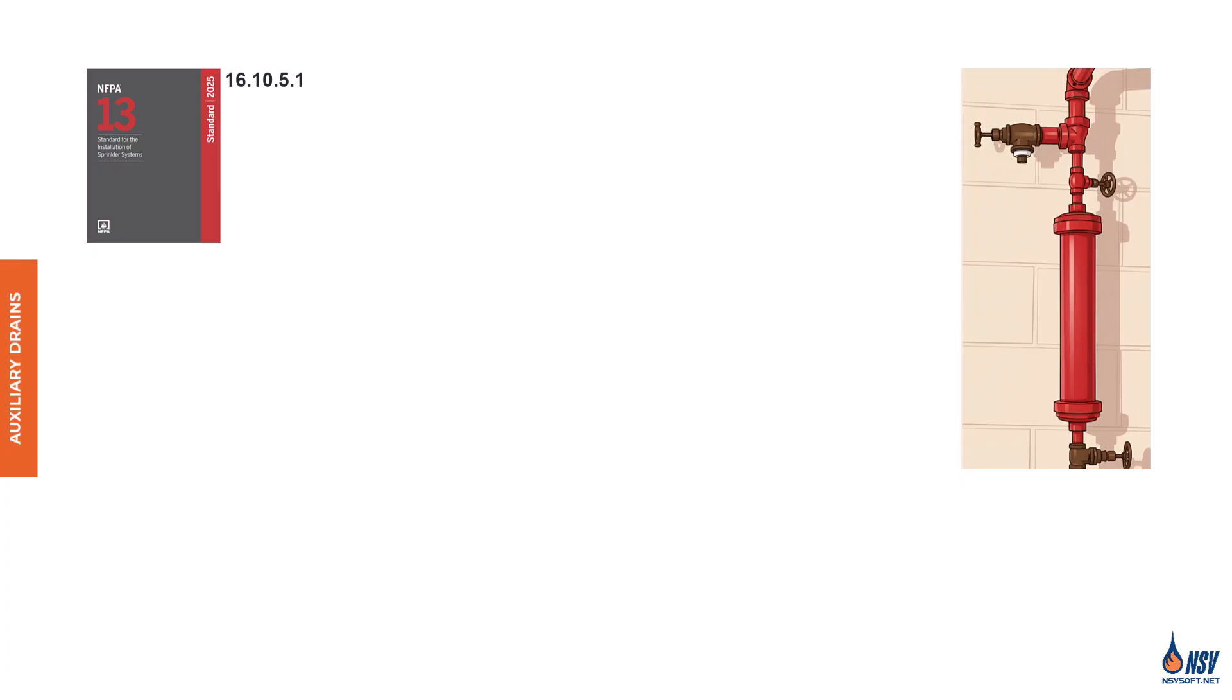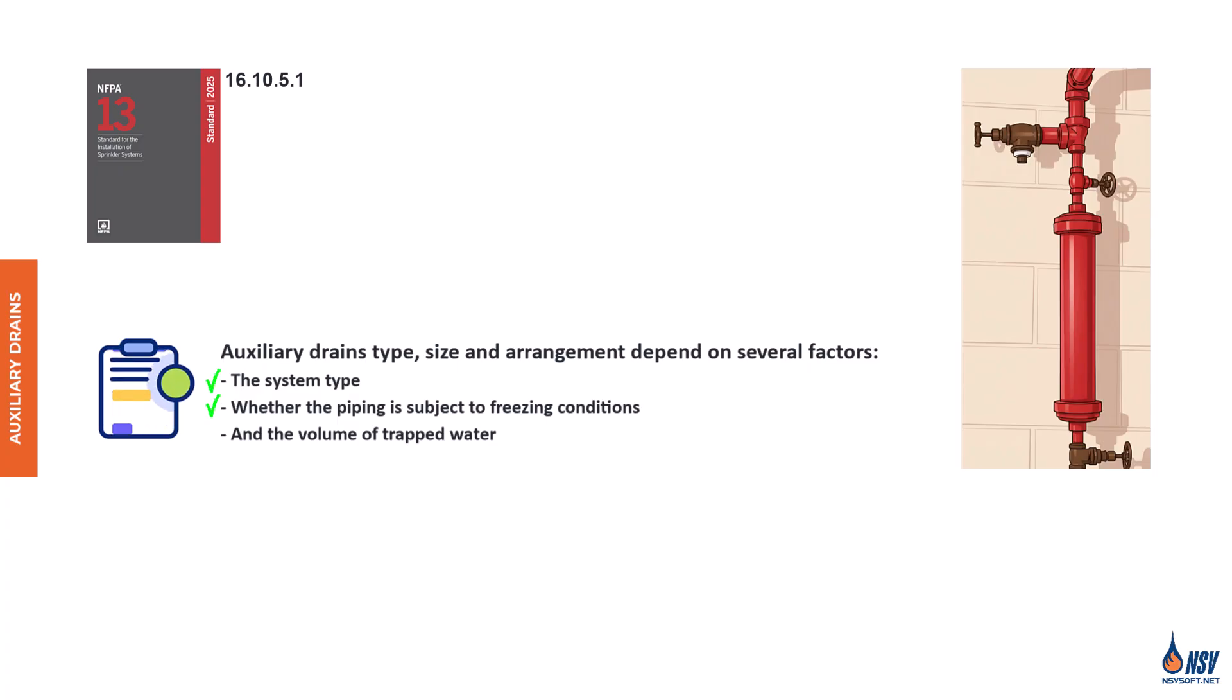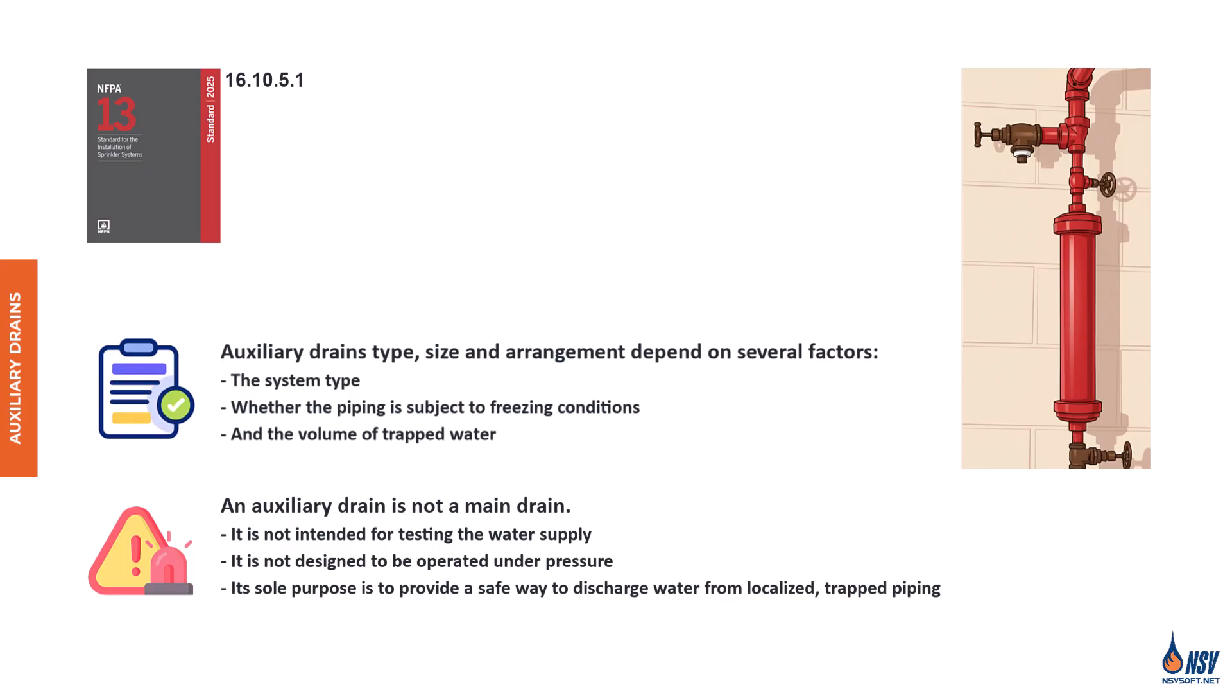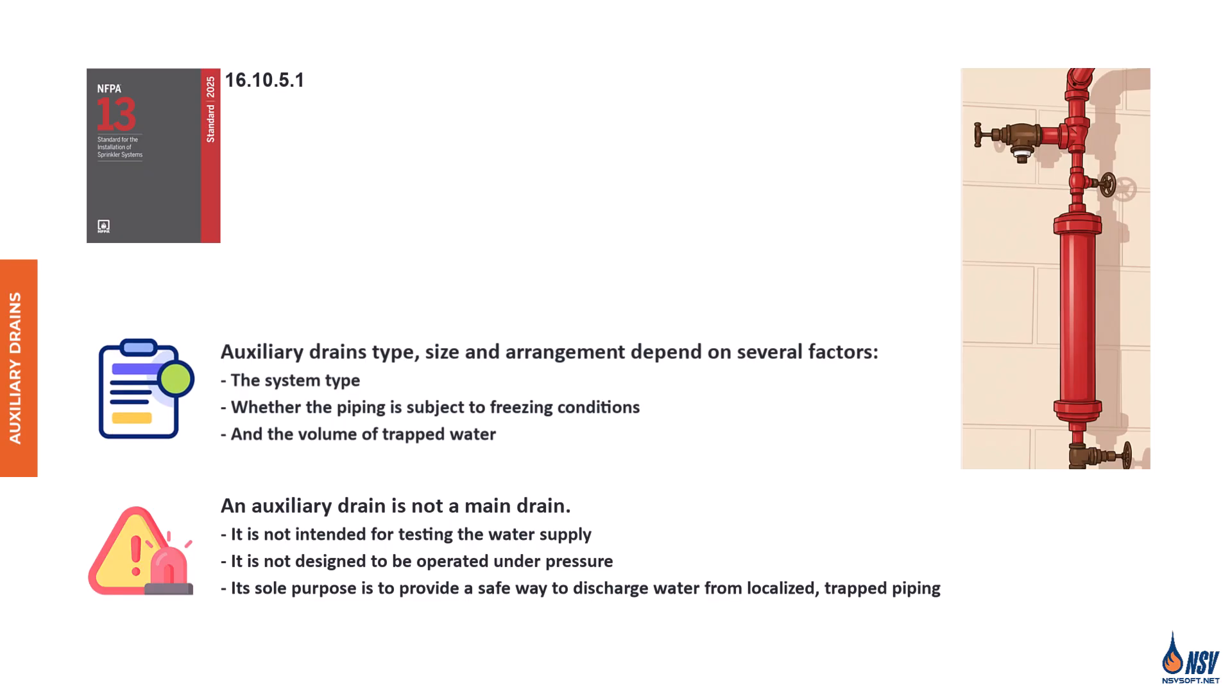According to Section 16.10.5.1 of NFPA 13, 2025 edition, auxiliary drains are defined as drain connections installed to remove water from a trapped section of pipe. They shall be provided wherever a change in piping direction prevents drainage of system piping through the main drain valve. Auxiliary drains are essential for trapped piping. Their type, size, and arrangement depend on several factors: the system type, whether the piping is subject to freezing conditions, and the volume of trapped water. An auxiliary drain is not a main drain. It is not intended for testing the water supply. It's not designed to be operated under pressure. Its sole purpose is to provide a safe way to discharge water from localized trapped piping. So, this distinction is critical for understanding the role of auxiliary drains in sprinkler systems and ensuring proper compliance with NFPA standards.